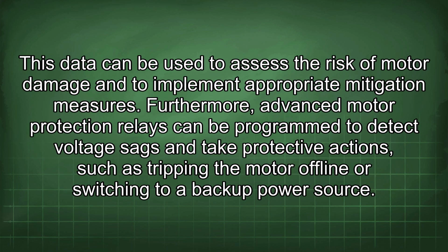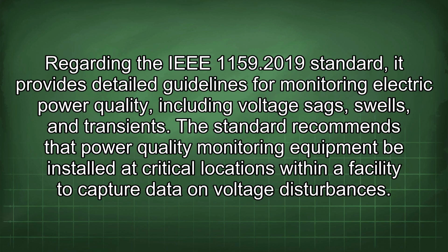This data can be used to assess the risk of motor damage and to implement appropriate mitigation measures. Furthermore, advanced motor protection relays can be programmed to detect voltage sags and take protective actions, such as tripping the motor offline or switching to a backup power source. Regarding the IEEE 1159.2019 standard, it provides detailed guidelines for monitoring electric power quality, including voltage sags, swells, and transients.